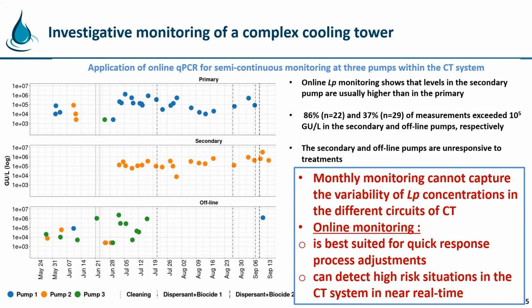Knowing that the monitoring plan in this cooling tower system is to measure Legionella by plate culture monthly, this plan cannot capture the variability of LP concentration in the different circuits of the cooling tower. As you see, online monitoring is best suited for quick response processes, since we get results during the day, and it can detect high-risk situations in the cooling tower system in near real time.